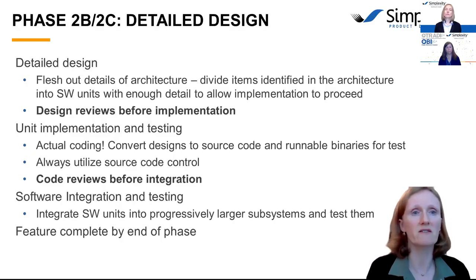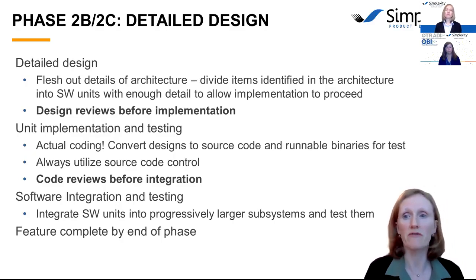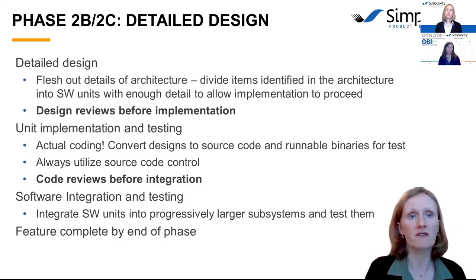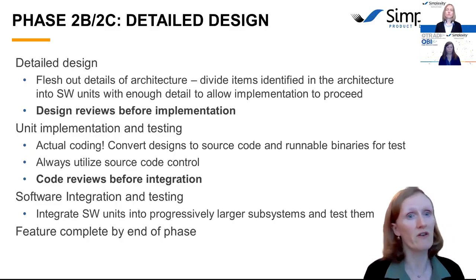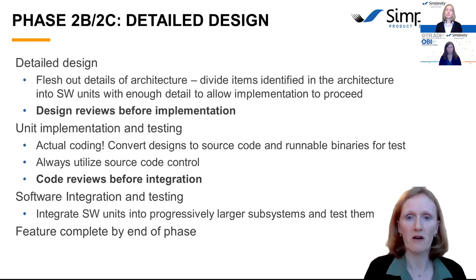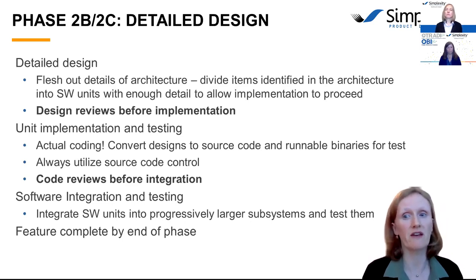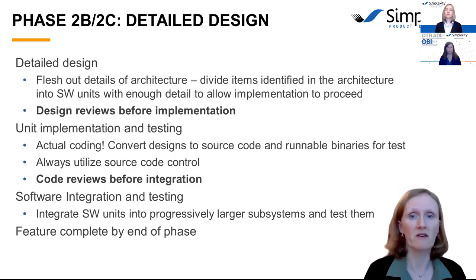The hardware has to be tested using functional software or firmware. So one effective strategy is to determine what software features are necessary to verify the hardware. And completion of those features can serve as a milestone, which you would have outlined in the software development plan for the earlier phases. By the end of the final design, build, test phase, though, the software must be feature complete and tested.